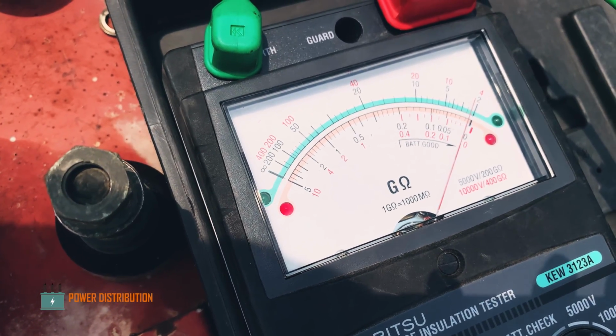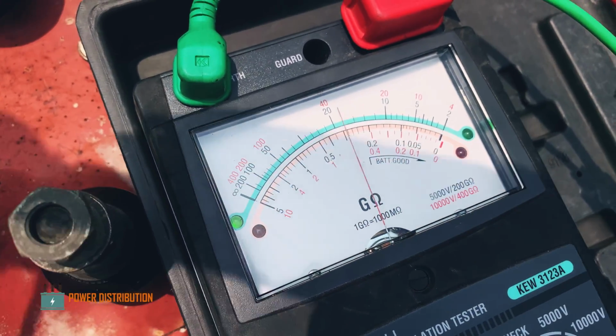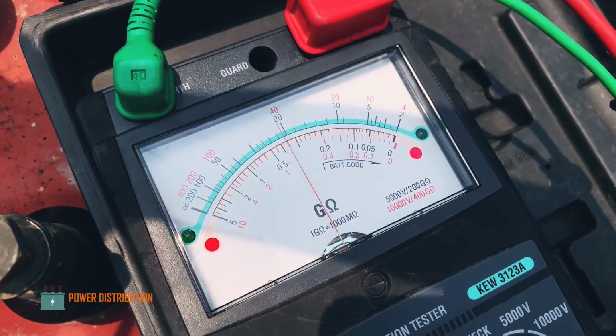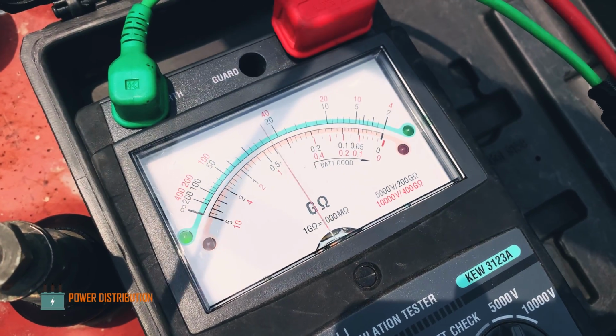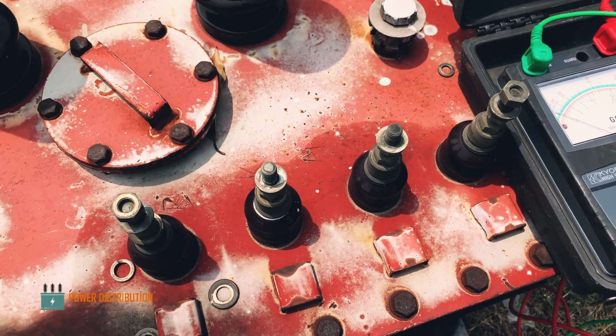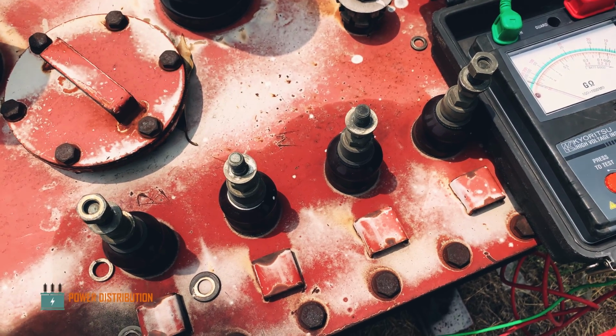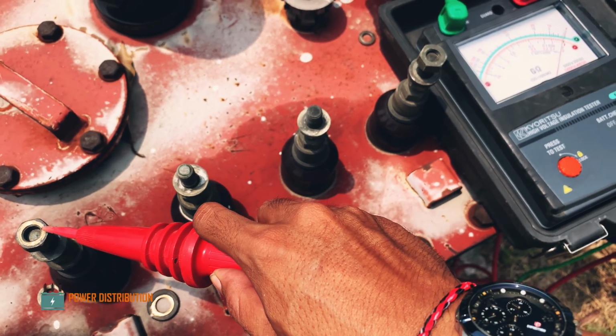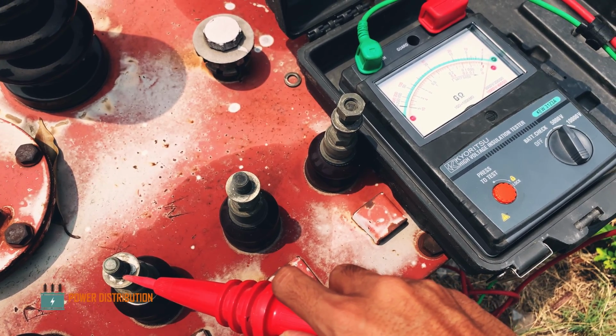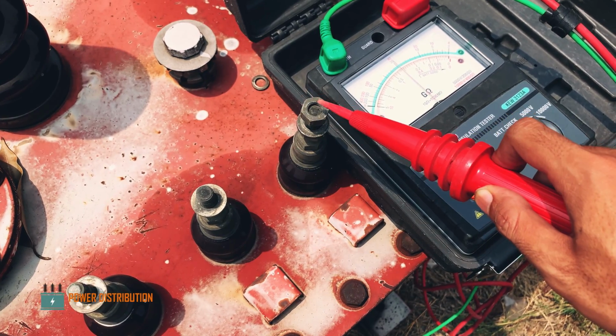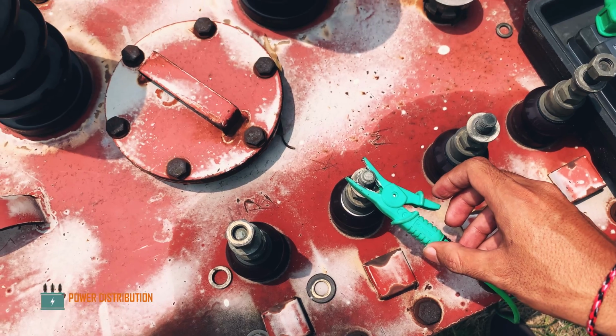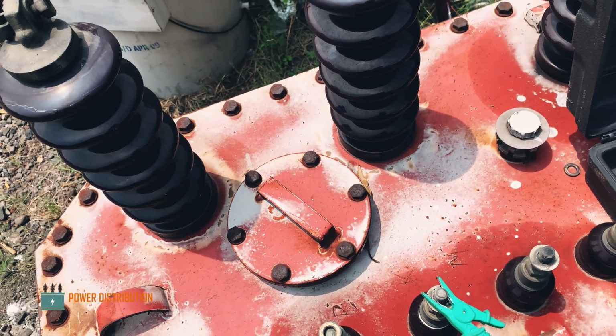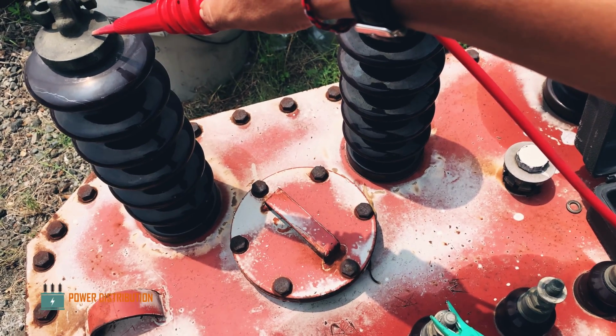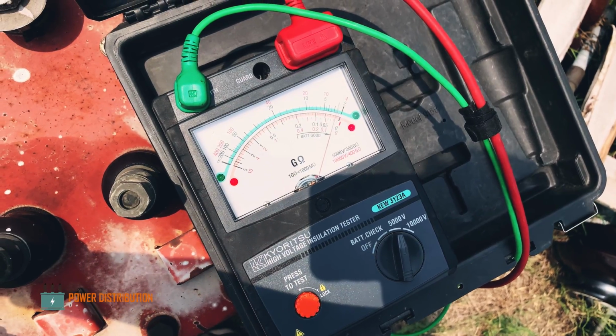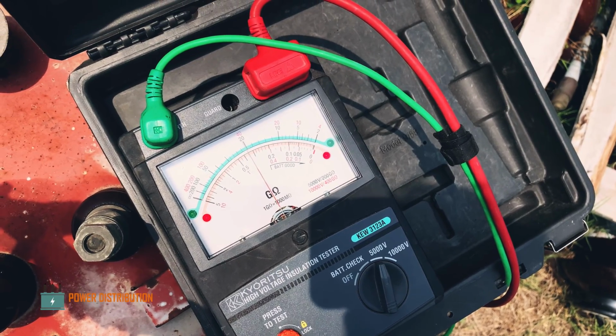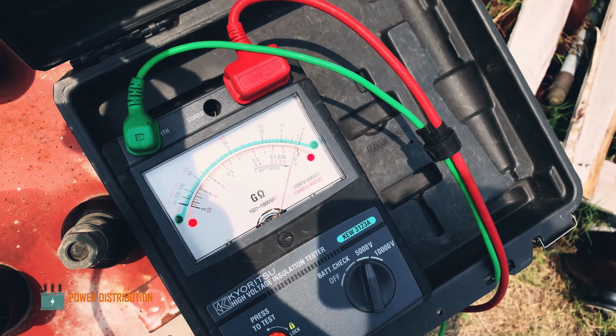Immediately it shows a zero reading for phase A, then some reading on phase B, zero reading on phase C. For the secondary terminal, visually also a zero reading for all the terminals. Now, for the sake of our demonstration, we will also measure the resistance between the primary and the secondary windings. As you can see, immediately it shows a zero. Some reading on phase B indicates some breakdown on the winding conductor.